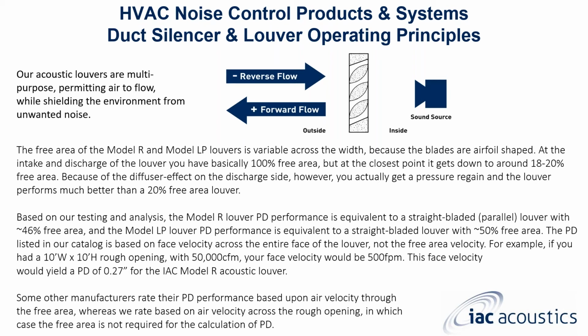I like to hit on this because a lot of people like to do percent of free open area first versus noise. Taking care of noise, taking care of performance, I say do performance first. At the intake and discharge of the louver, you have 100% free area, so a 10 foot by 10 foot opening. At the closest point on louvers, whether it's ours or anybody else's, you're going to be 18, 20, maybe 30% free open area, because of the diffuser effect on the discharge side, you get a pressure regain. And the louver performs much better than 20% free open area. Based on our testing and analysis with the louver testing criteria, the Model R louver pressure drop performance is equivalent to a straight bladed parallel louver with 46% free open area.